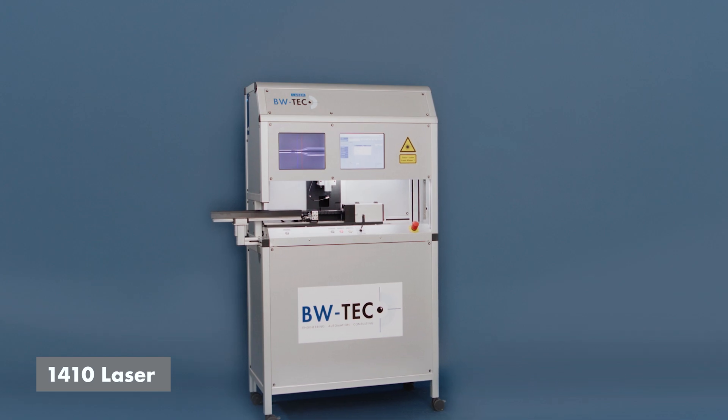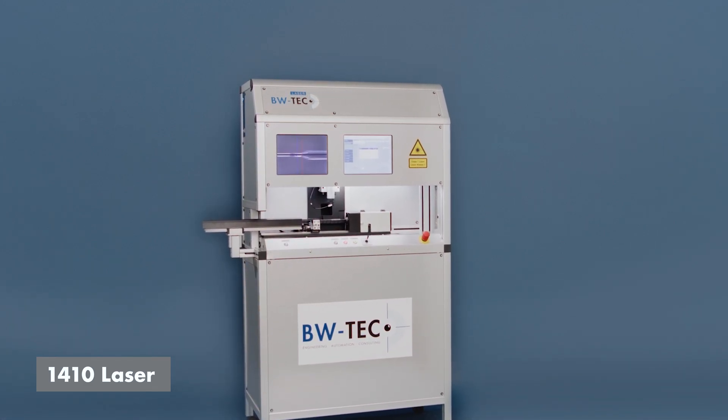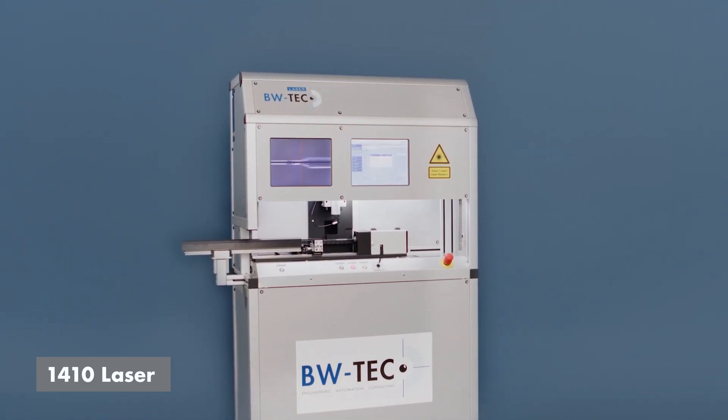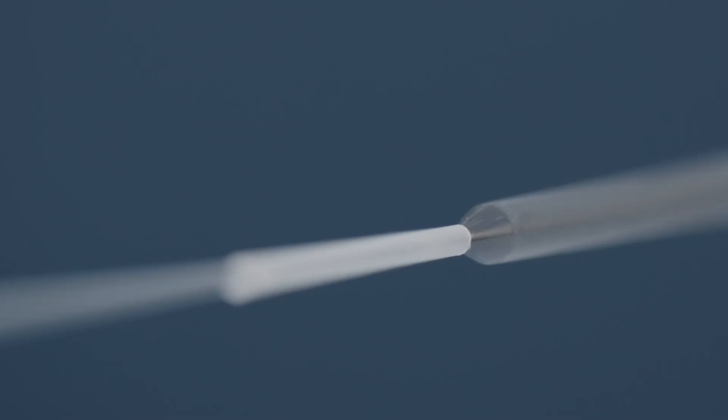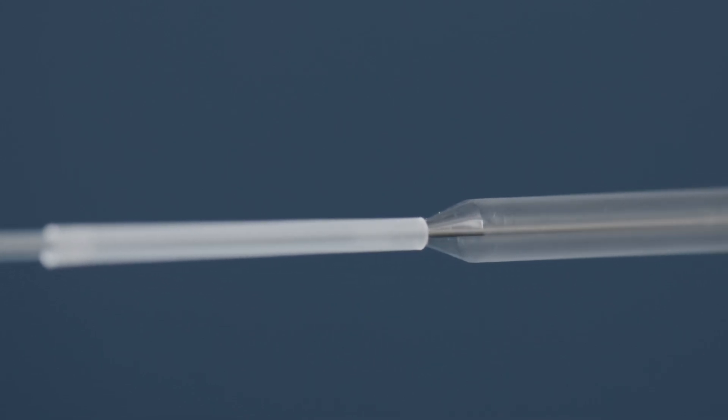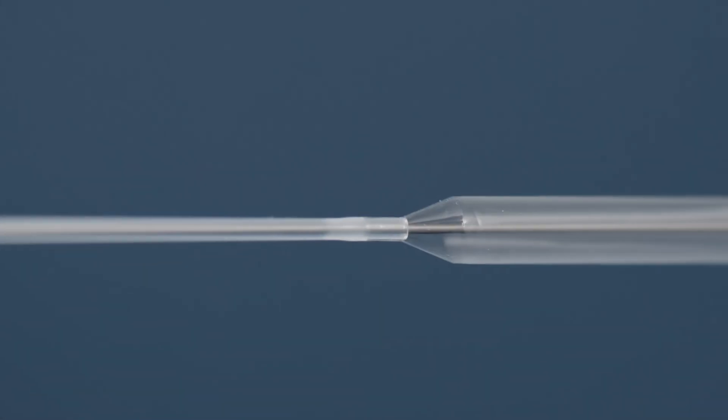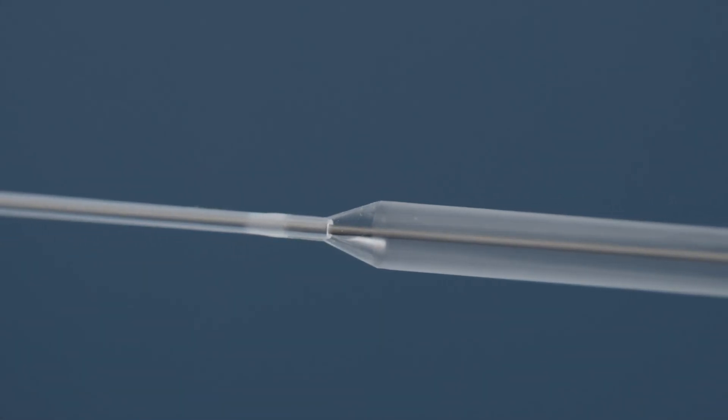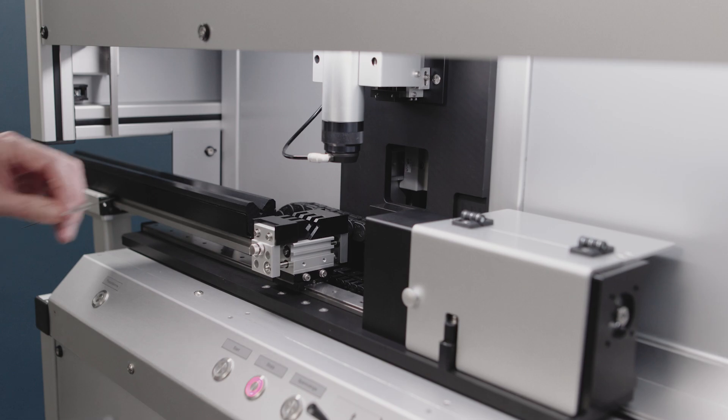The BWTEC 1410 laser welding machine is used to connect fine plastic tubing, ideal for welding of the distal and proximal side of PTCA and PTA balloon catheters.